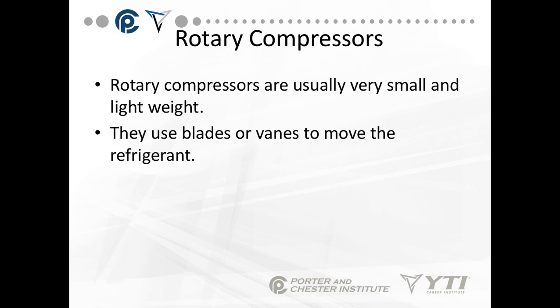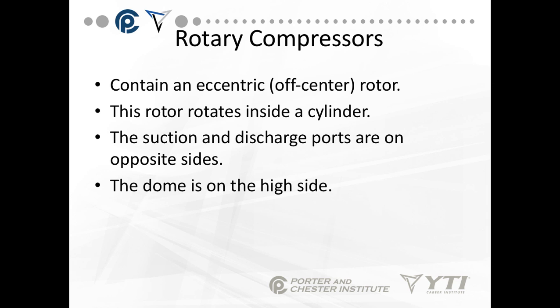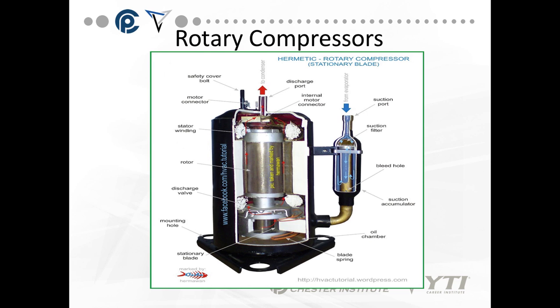Rotary compressors — we're going to start with these because they're the smallest. They're usually very small and lightweight. They use blades or vanes to move the refrigerant; it's not a piston-type action. They contain an eccentric, which is just off-center — the shaft is not in the center of the rotor so it moves side to side. The rotor rotates inside a cylinder, and the suction and discharge ports are on opposite sides.